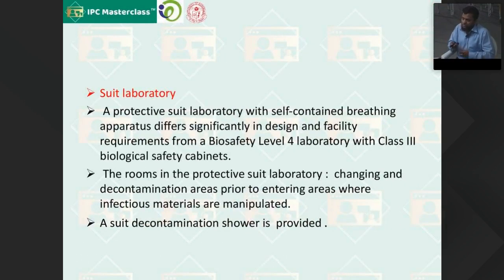Apart from that, if you see in the suit laboratory, this is another type of BSL-4 laboratory where you require a protective suit laboratory with self-contained breathing apparatus. It differs significantly from the class 3 biosafety cabinet laboratory. How? It does not need Class III cabinetry because here the person will wear a breathing apparatus, a HEPA filtered one.